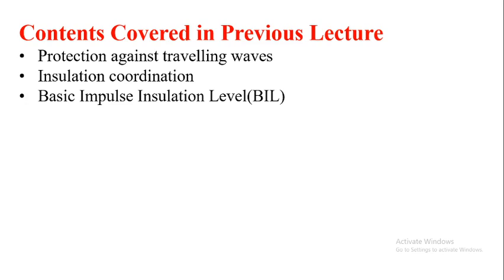a protective device, because these traveling waves will not be protected with the help of a shielding method, that is with the help of ground cables. It is not possible to prevent the effect of the traveling waves. For that, in order to give protection against these traveling waves, we need to make use of different types of equipments known as a rod gap, arcing horn, lightning arrestor, also known as surge diverters, and we use the surge absorber. The detailed explanation of all these points was discussed in the previous lecture.